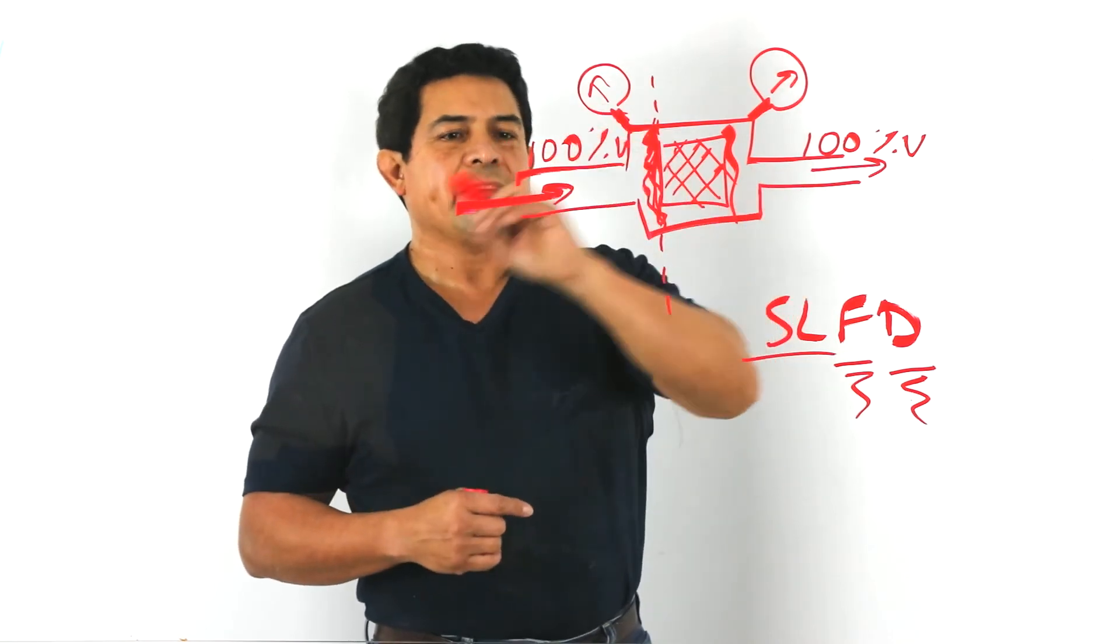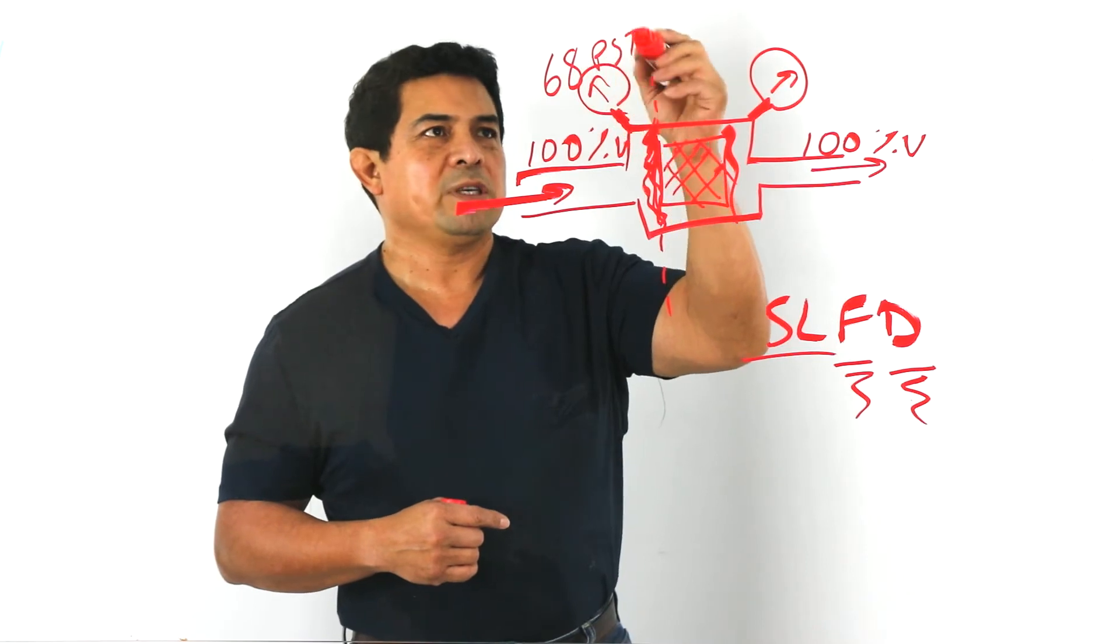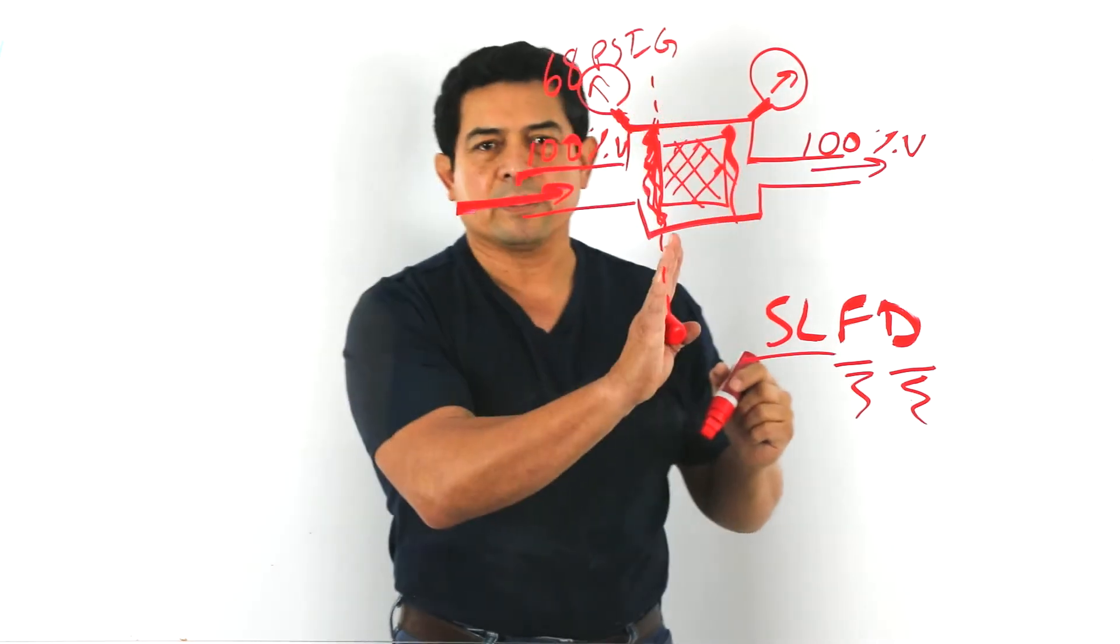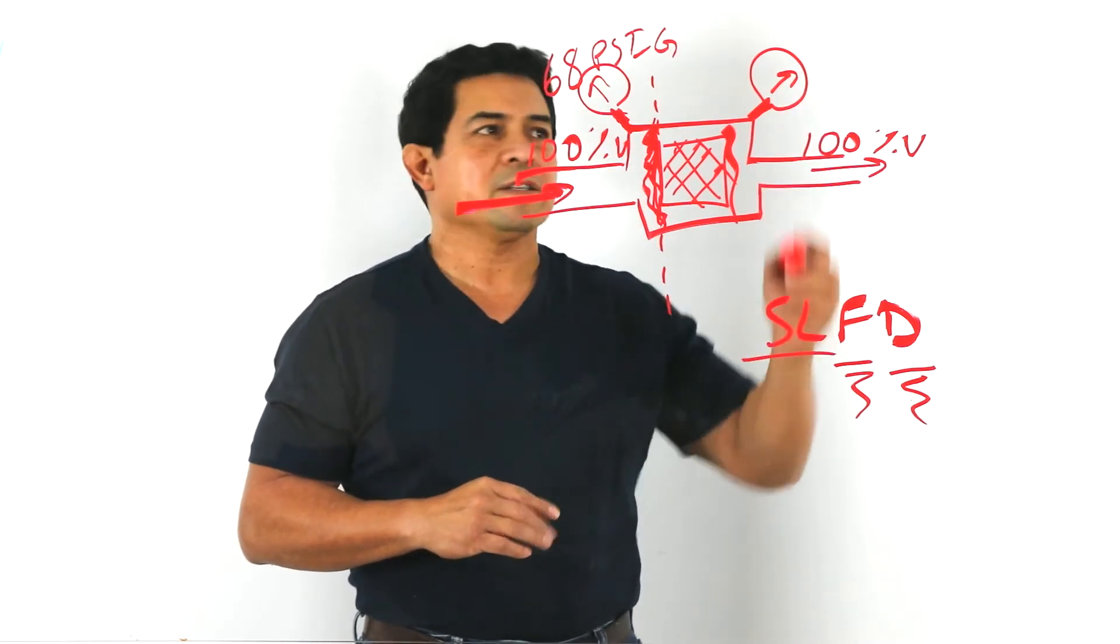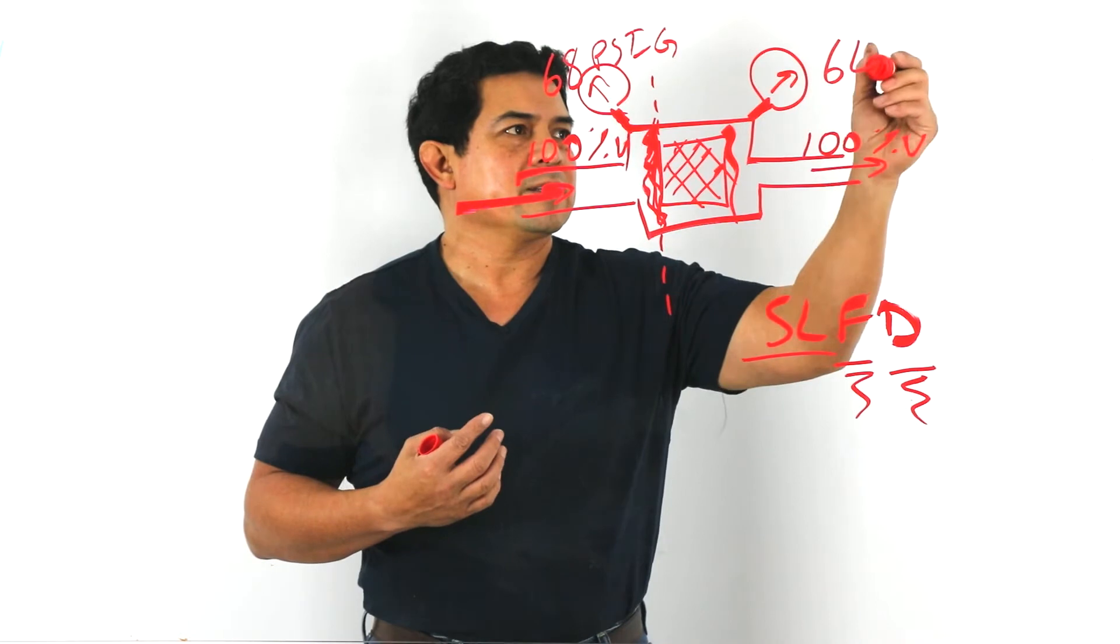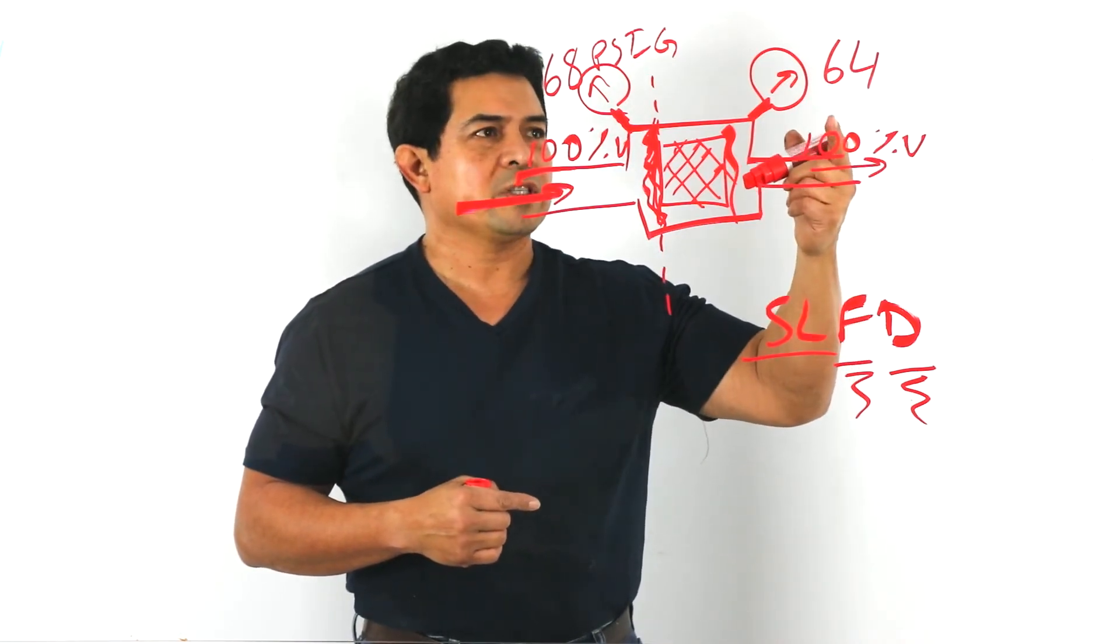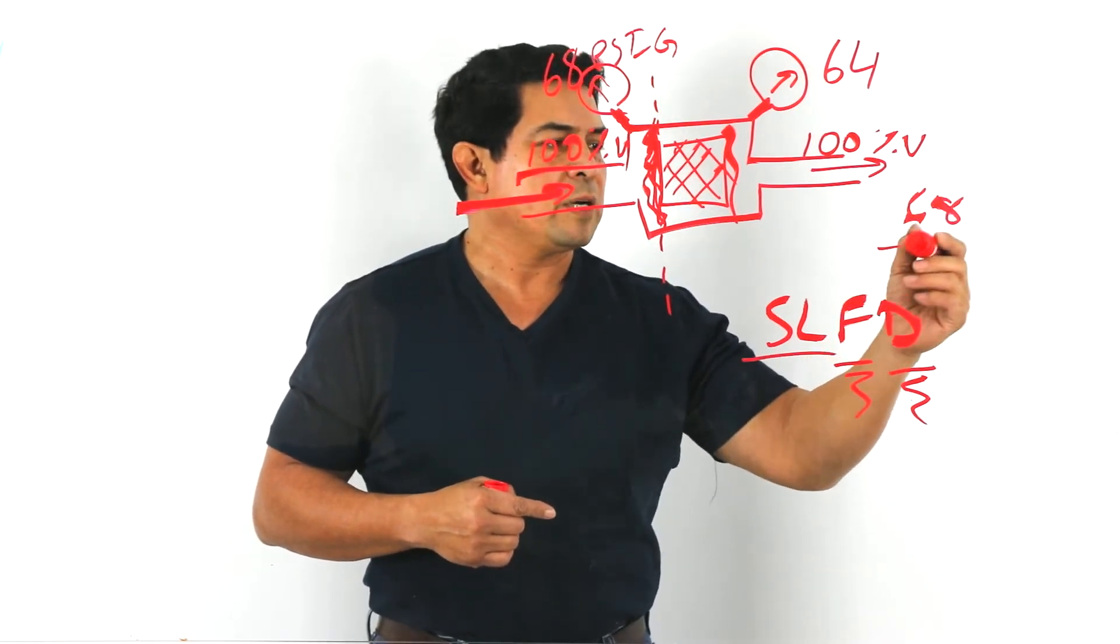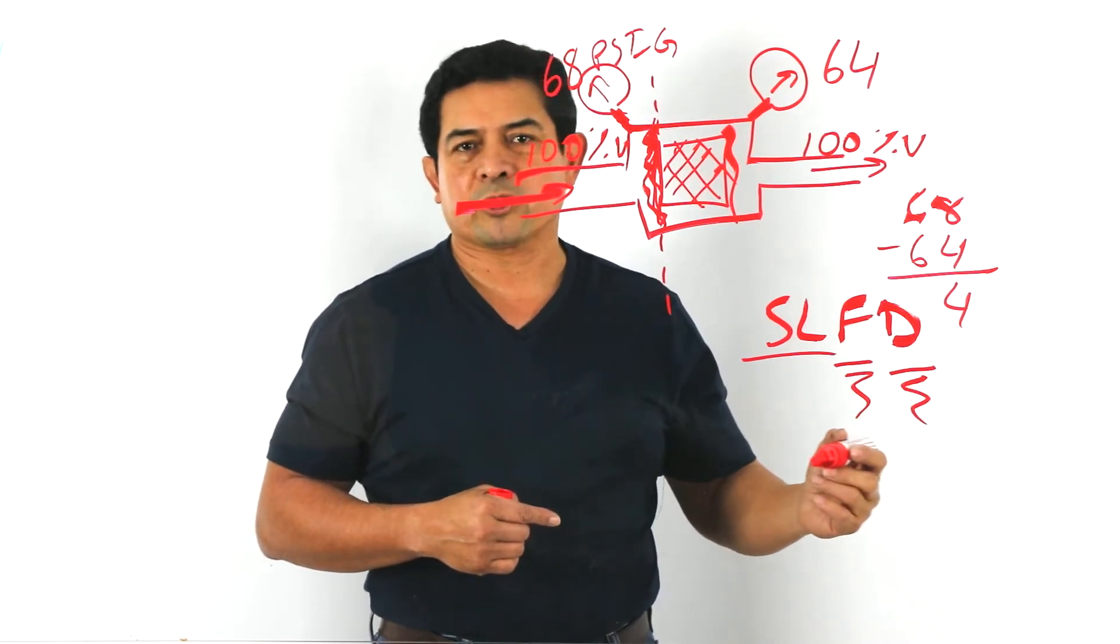So let's say that refrigerant is traveling in this direction and we have 68 psig here. This is creating a restriction, so the pressure on this side now is going to be, let's say, 64. So now we see that's a lower pressure. We have 68 minus 64. That gives us 4 pounds of pressure difference.